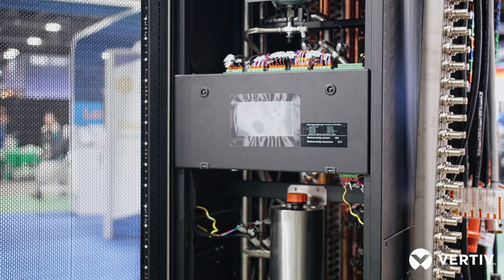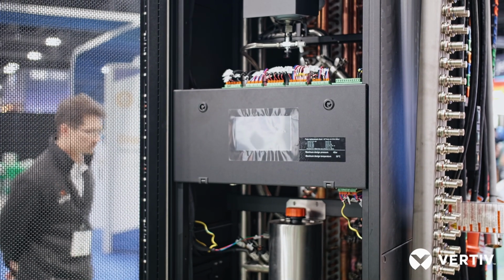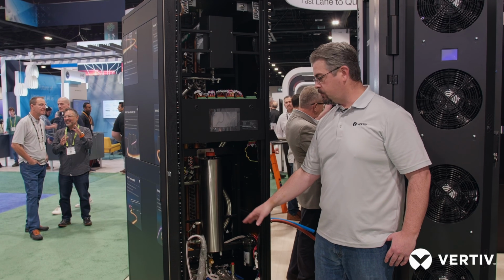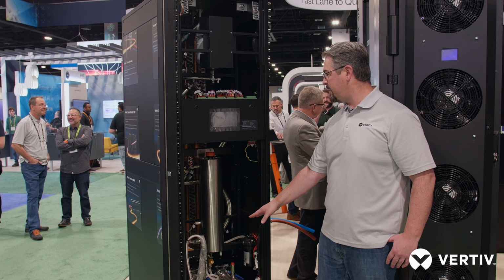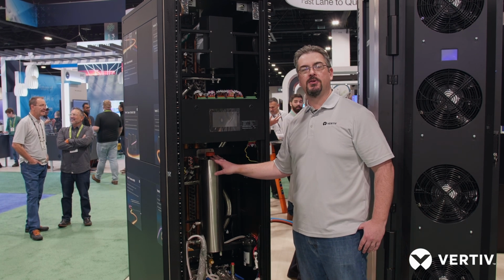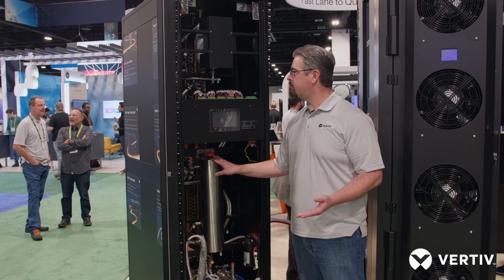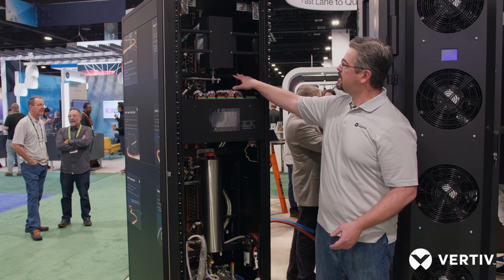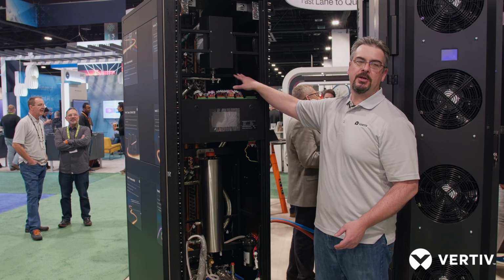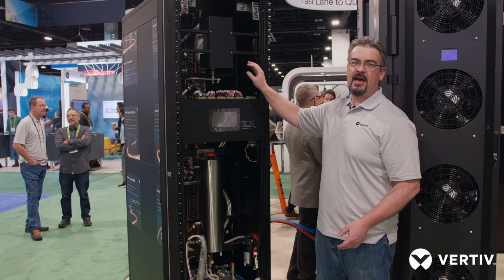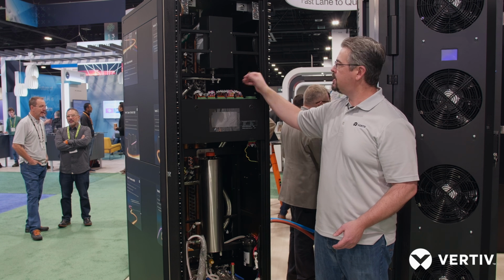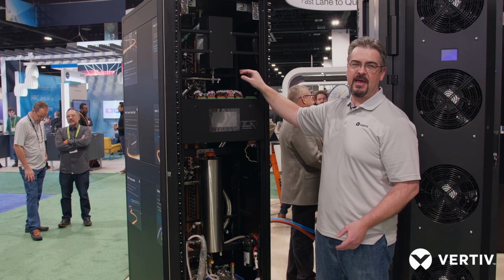Looking at the other side here, you can see a lot of the same design philosophy. You know, two redundant pumps with independent filtration for concurrent maintainability. Same stainless steel reservoir for fluid makeup as air is removed from the system. And on the inside here, you can see the actual liquid-to-air heat exchanger itself, where we're pumping that hot return fluid from the cold plates through the heat exchanger and then rejecting that heat back to the cold aisle via air.